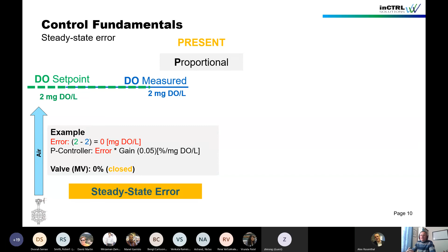This is called a steady state error. Two solutions to that: one, if you do a proportional controller only, you can introduce a bias. You decide on average how much air you need, and the P controller works around the set point. But then you have to set that bias term manually - something you have to watch and adjust.